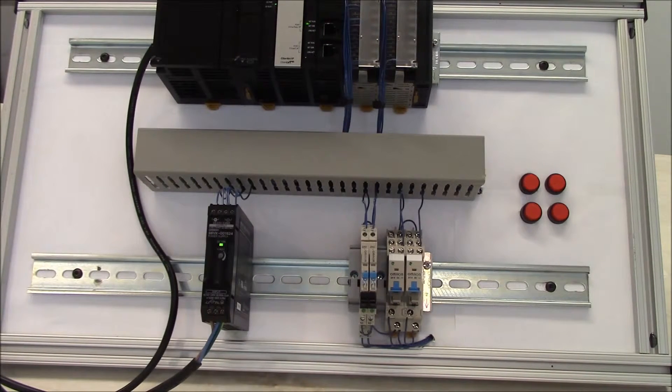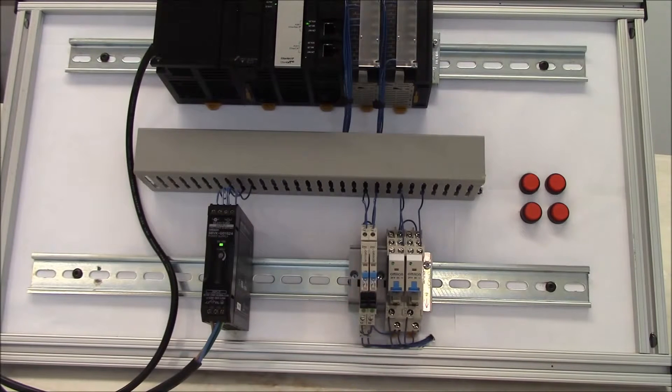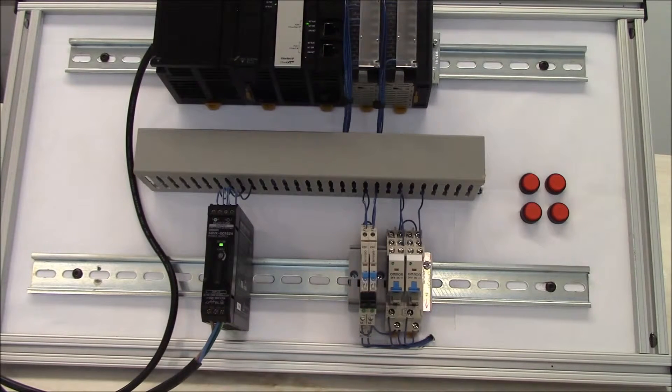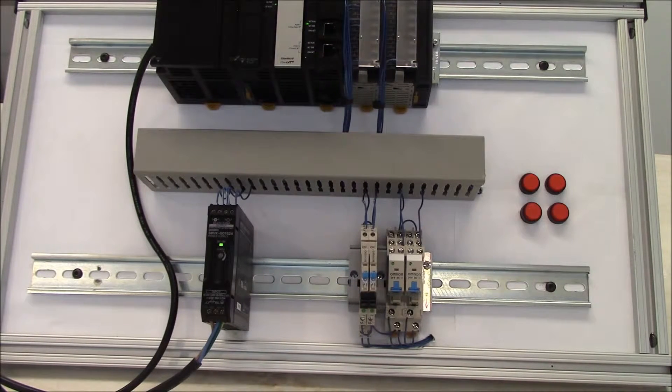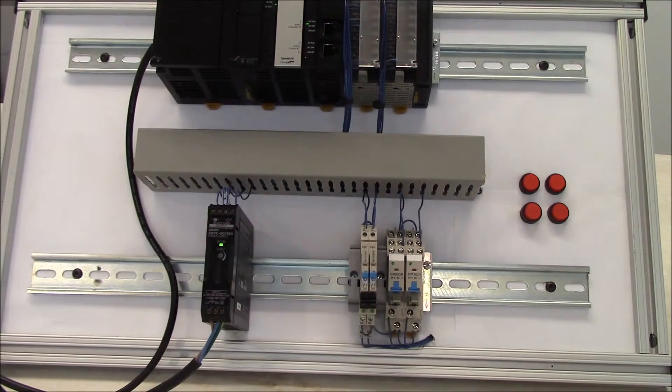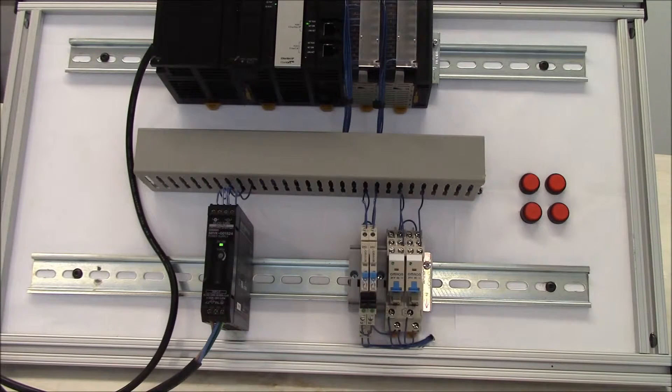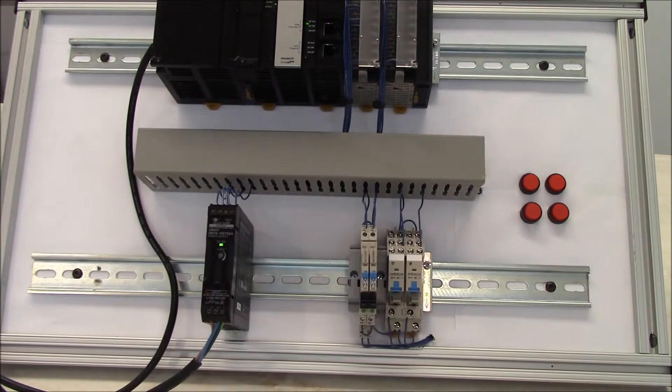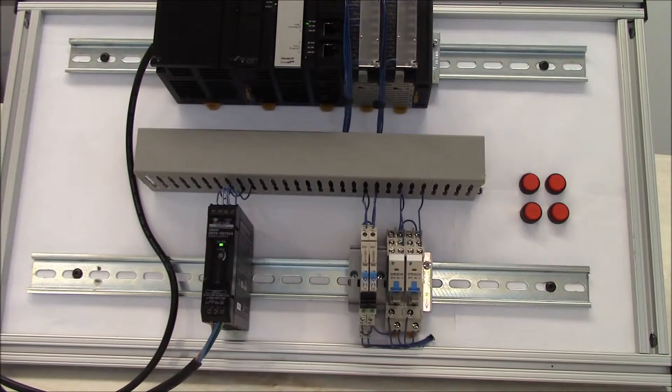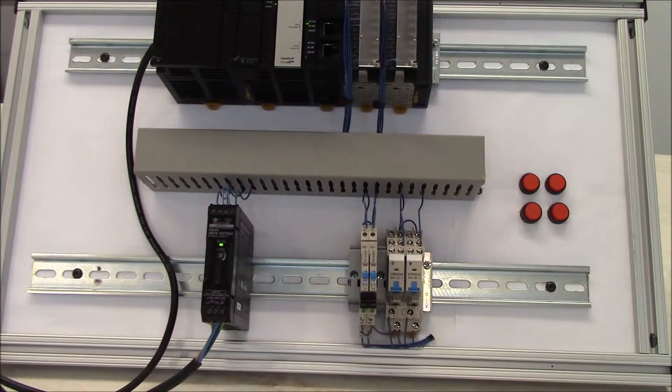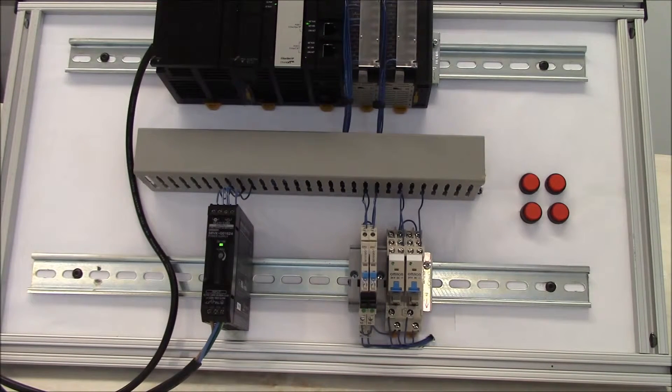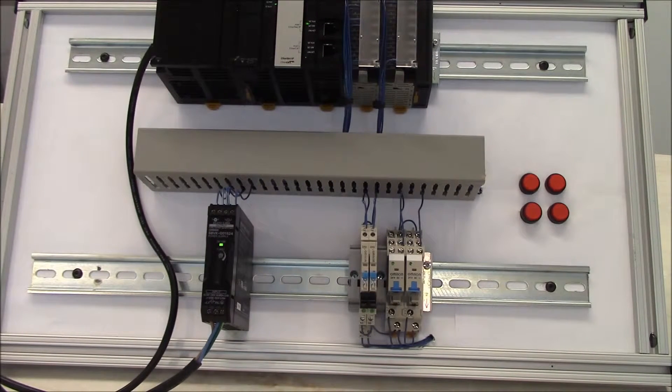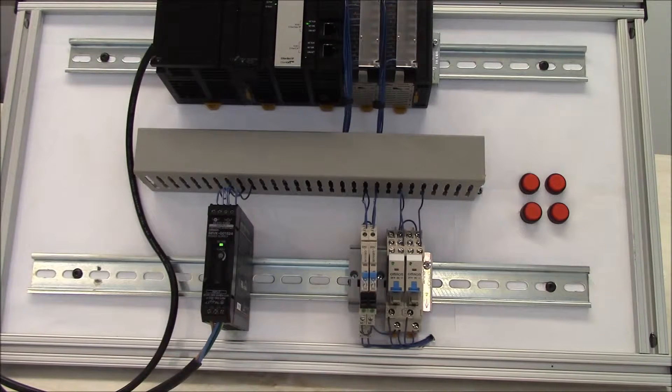The package itself comes in 6.2 millimeter wide to save space. We do offer a 6 amp contact rating on that and you can get anywhere between 100,000 to 200,000 electrical operations depending on the current you're running through the contact.